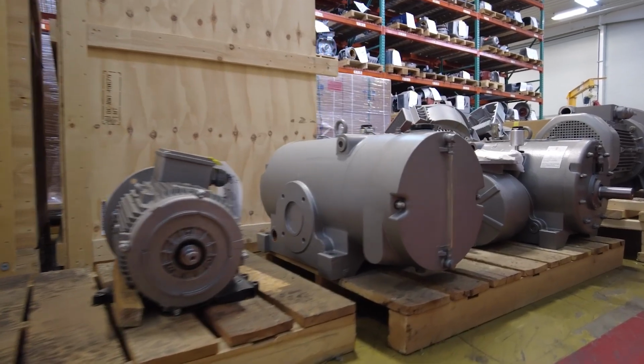The right way to wire a pump is really going to be dependent on the motor that's installed. So every motor will have its own wiring diagram that will show you what configurations are acceptable to run each of the voltages listed on the motor. So it's very motor dependent. When customers go to wire their pumps up for the first time, we see that they just wire in their power leads and they're not checking the actual wiring diagram that comes with the motor to make sure that the motor is configured for their voltage supply.